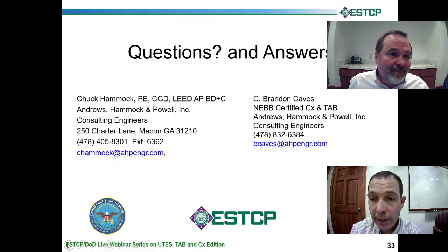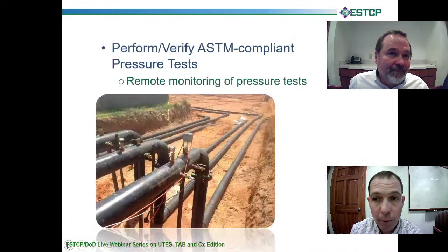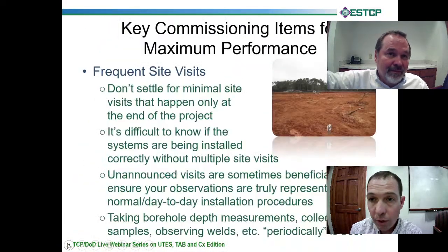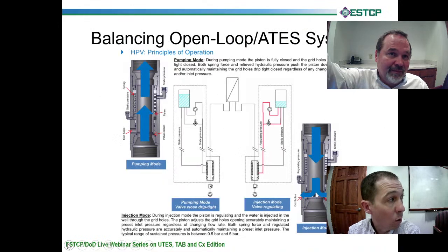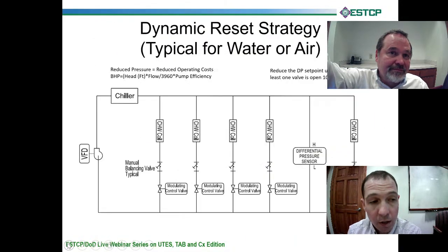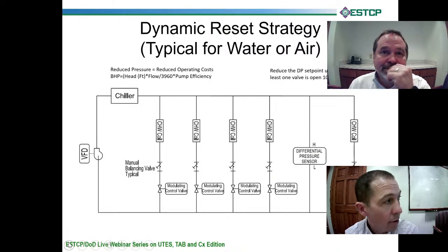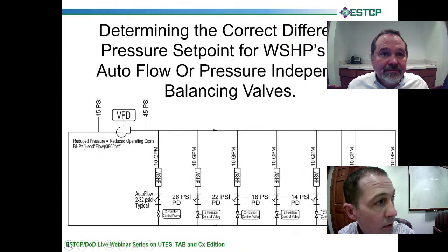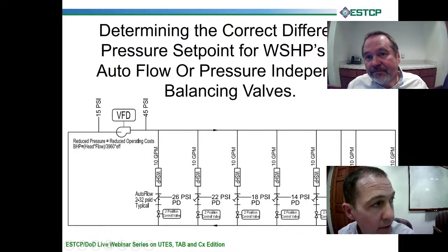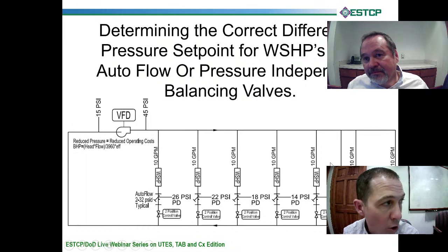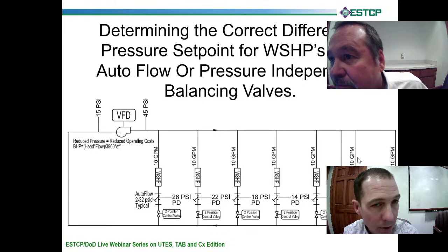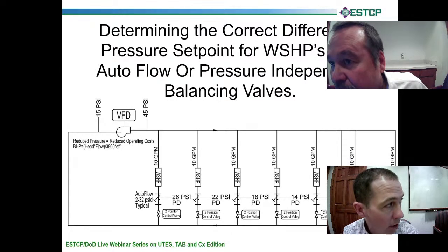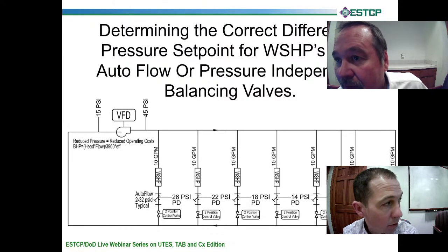Yeah. I mean, the problem is that once you get down to 2 psi, your valve's wide open, and you don't know if it's receiving design flow or if it's receiving less than design flow. So when we balance a system with automatic flow control, go back one more slide, Chuck, please. Yep, that's it. So when we balance a system with automatic flow control valves, the most remote valve, we will not try to hit quite 2 psi, maybe like 3 psi or something, and that's very close. I mean, that's getting you pretty close to your minimum pump speed for that particular scenario.